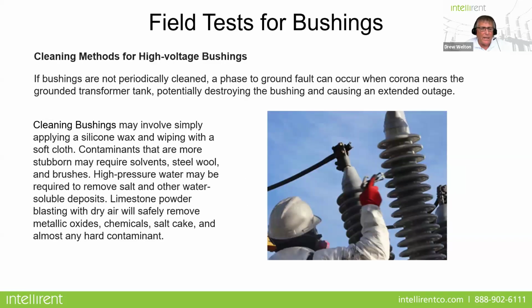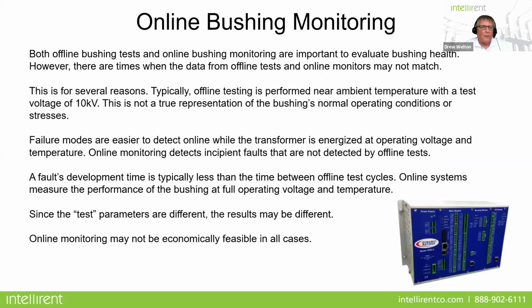Now, cleaning. Everybody asks, how do I clean a bushing? It's important to clean the bushings, not only to get accurate power factor measurements, but also to improve the durability of the porcelain. Depending on the environment, sometimes you have to use high pressure water to clean them, or limestone powder blasting. But the one thing that's always good for cleaning your bushing is a good silicone wax designed for cleaning bushings. It doesn't change the thermal temperature of the porcelain, so it won't affect your test results, and it puts a nice protective layer on the bushing itself.